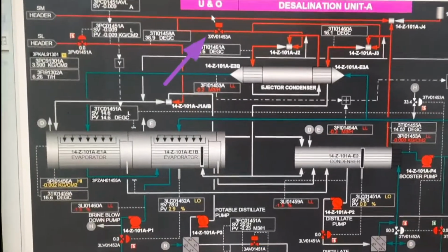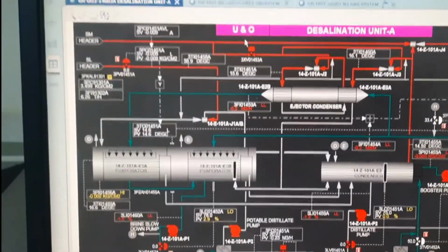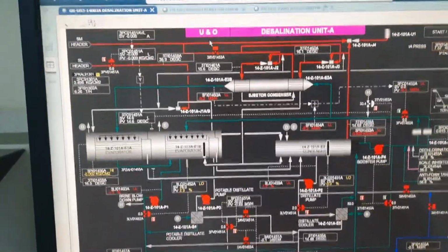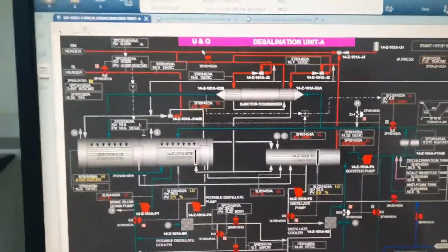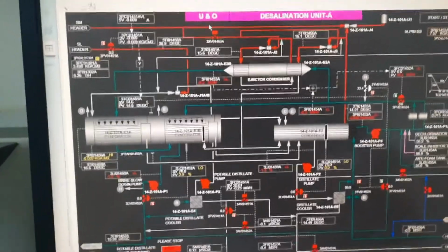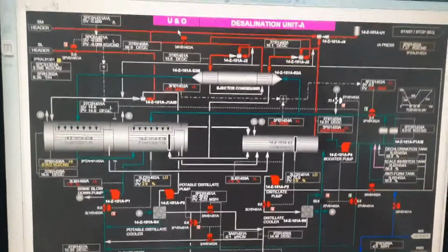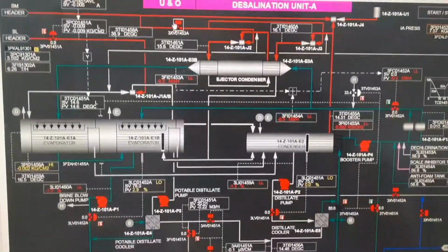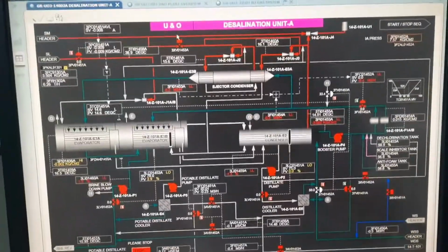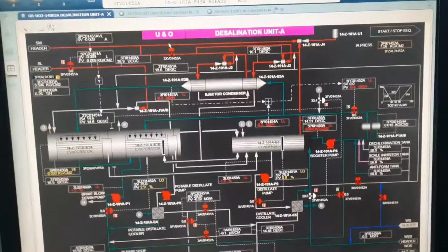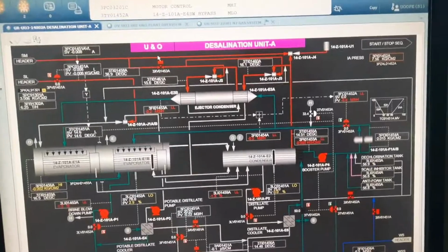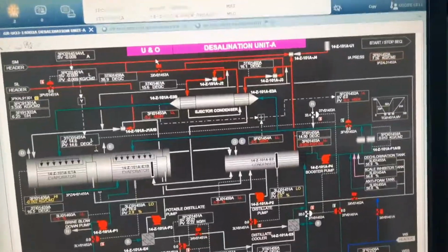On the local side, the SM control valve has one bypass valve, and the hogging ejector has one drain valve; keep this drain valve slightly open. Then open this hogging ejector valve near the ejector condenser, and open the SM control valve bypass valve and start hogging. When the vacuum pressure reaches around minus 0.80, at that time stop hogging. So the vacuum pull-up is completed.